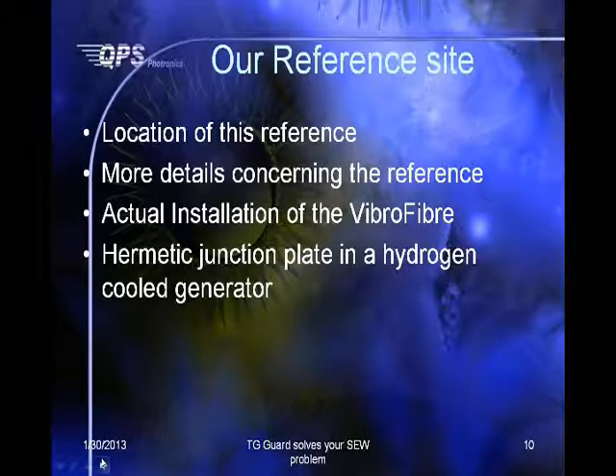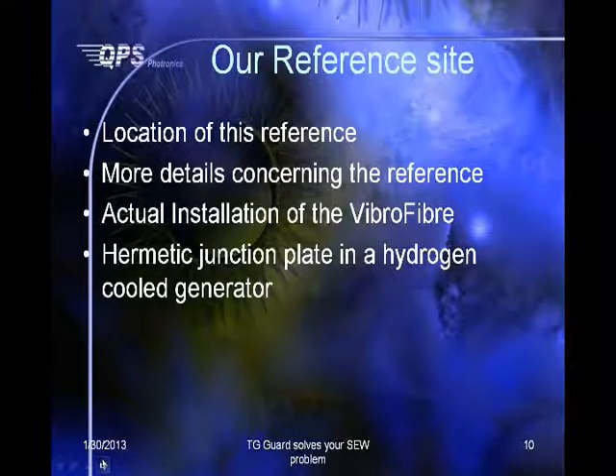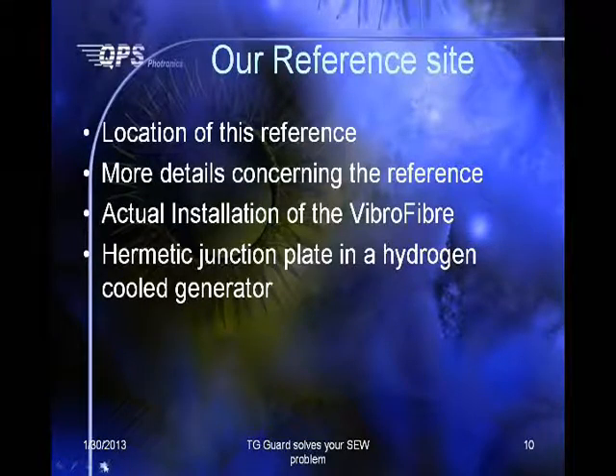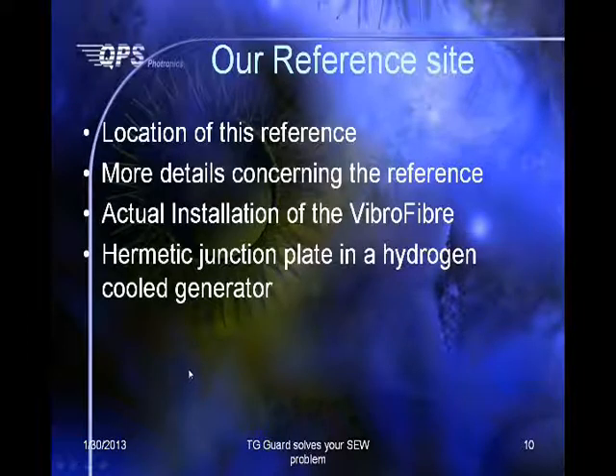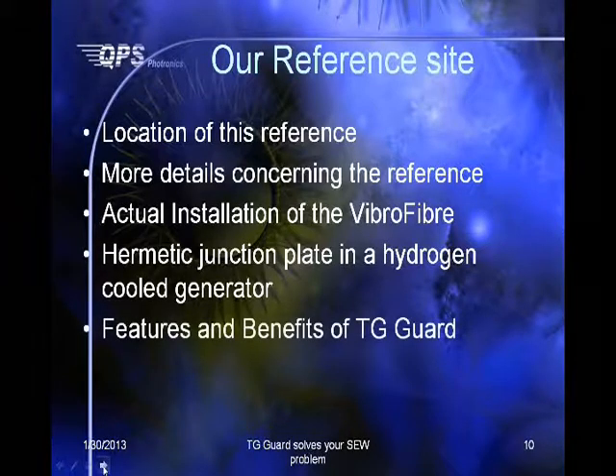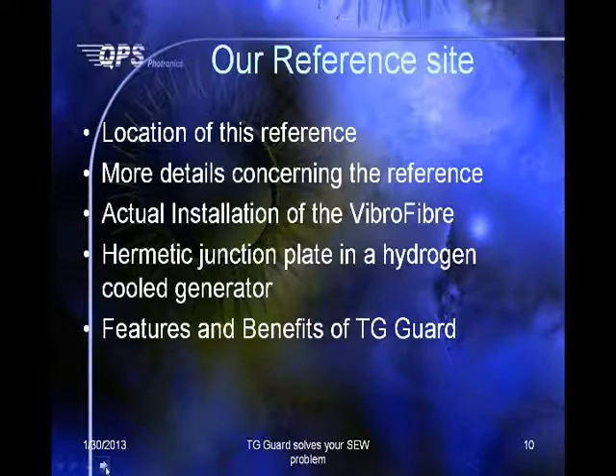The hermetic junction plate is critical in a large generator, because inside the generator you have 70 psi of hydrogen, and hydrogen can be an explosive environment if there should be any leak. So what you would like to do is minimize the number of holes you have to drill into your generator wall, because the larger the hole, and the larger the number of holes, the higher the probability of getting a leak. With that concept, we make a large junction plate, and more will be described about that.